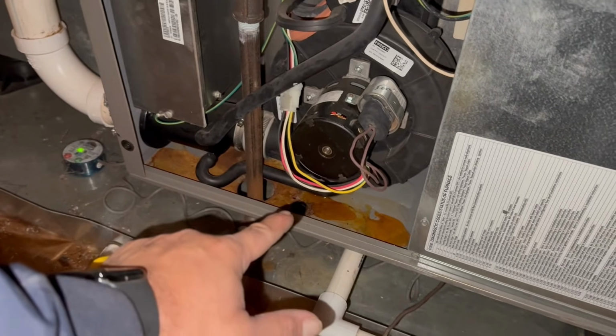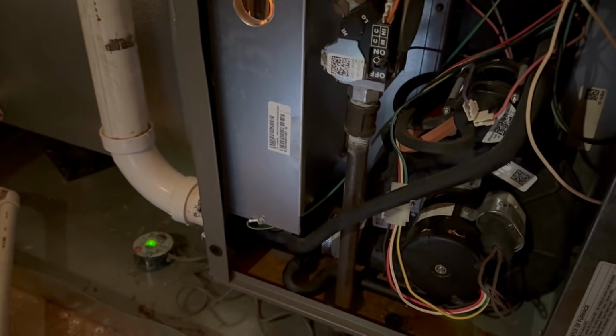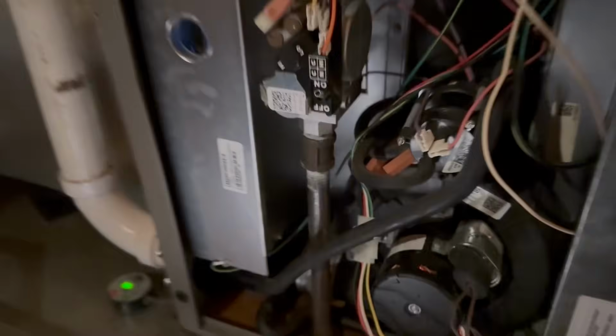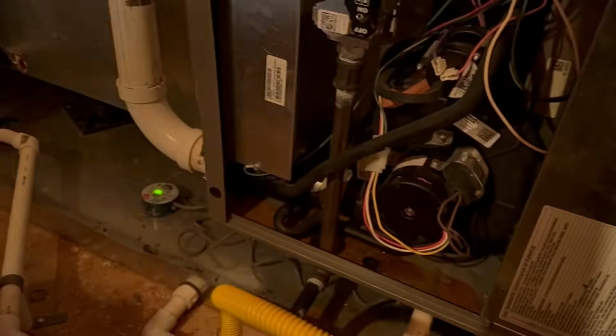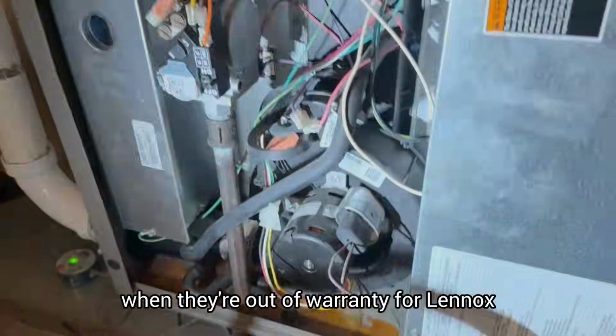Okay, inducer's on. Igniter's coming on. There's gas. The flame sensor's proving. Let's make sure we got blower. That could be why the limit locked out. Okay, it's kicking into high stage. This unit is from 2014, so it's out of warranty, unfortunately. These things can get expensive when they're out of warranty for Lennox.